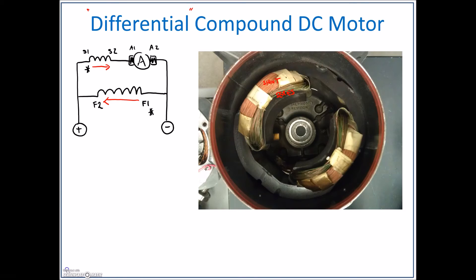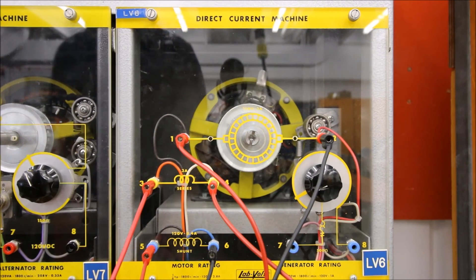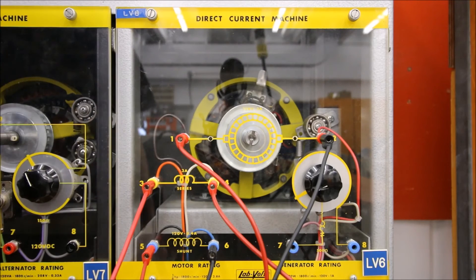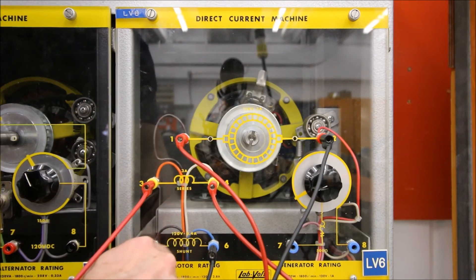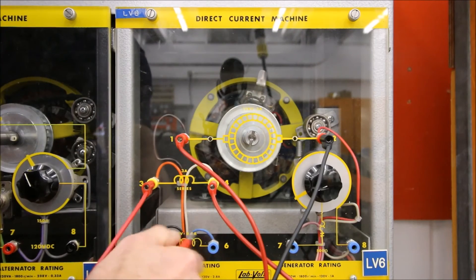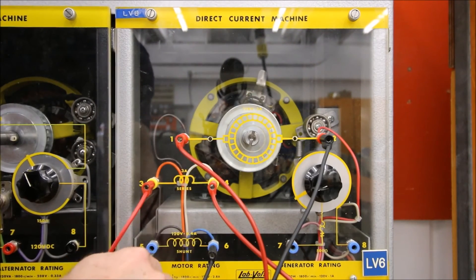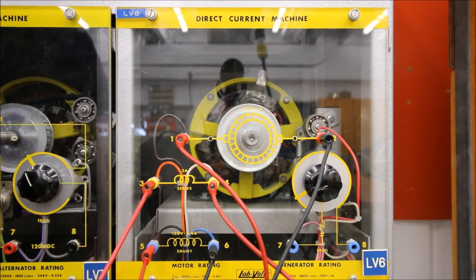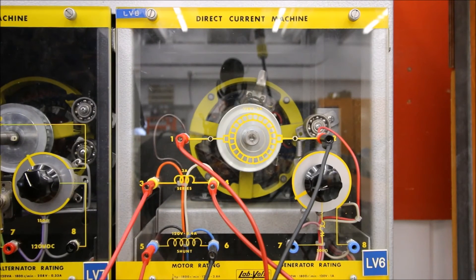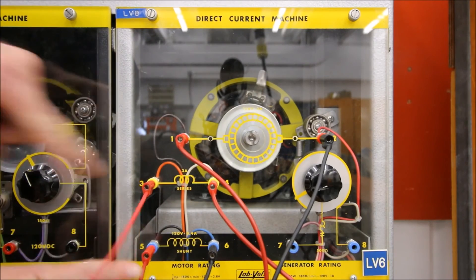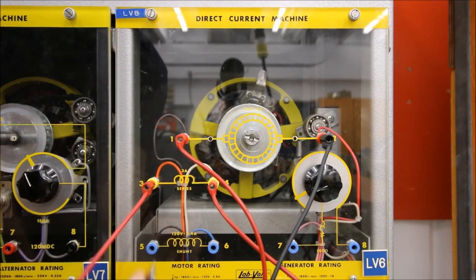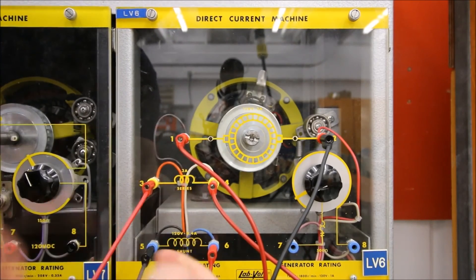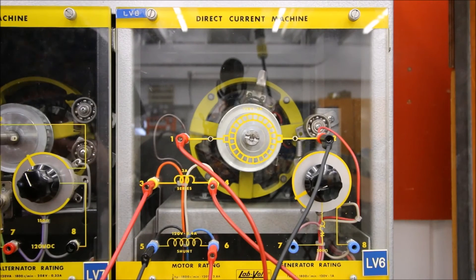Okay, we had the cumulative compound. Let's take a look at the differential compound. Differential compound means that one of the windings between the series and the shunt is going in the opposite direction. Let me show you normal operation. This is normal operation for the cumulative compound, meaning the series and the shunt are both having their magnetic fields going in the same direction. But I'm going to change the polarity of the shunt so the shunt is now going in the opposite direction of the series.